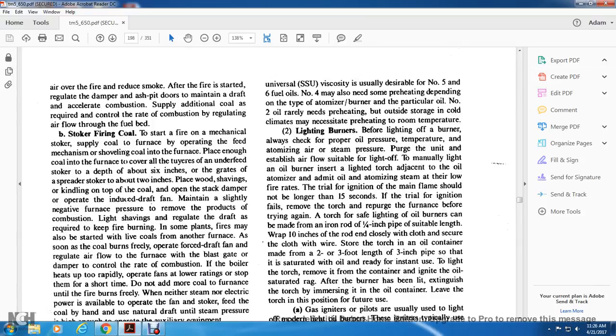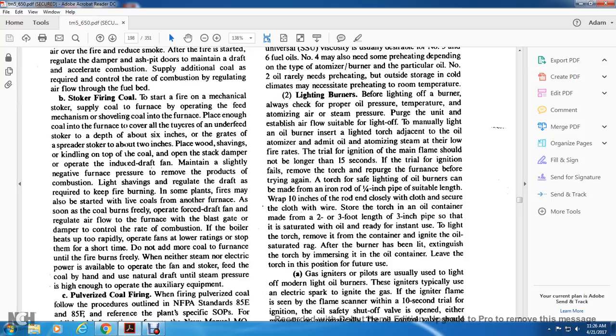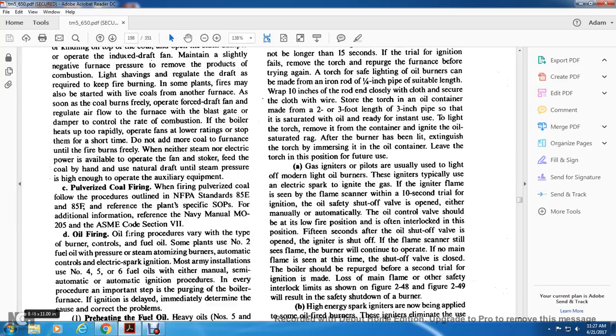Stoker firing coal: to start a fire with a mechanical stoker, operate the feed mechanism and place enough coal in the furnace to cover all the tuyeres on underfeed stokers to a depth of 6 inches or greater, or on grates of spreader stokers about 2 inches. Place wood shavings over the top of the coal. Open the stack damper, operate the induced draft fan, maintain slightly negative furnace pressure to remove the products of combustion. When coal burns freely, operate forced draft fans and regulate air flow to the furnace to control the rate of combustion. Do not add more coal to the furnace until the fire burns freely. Feed the coal by hand using natural draft until steam pressure is high enough to operate the auxiliary equipment.